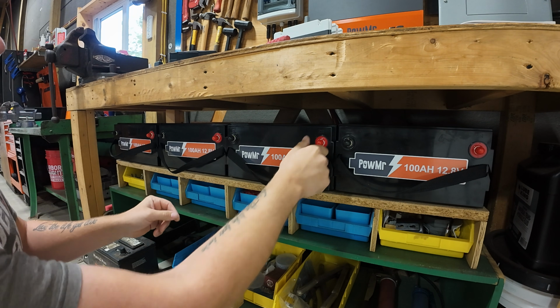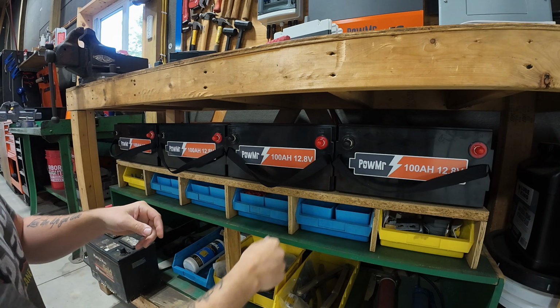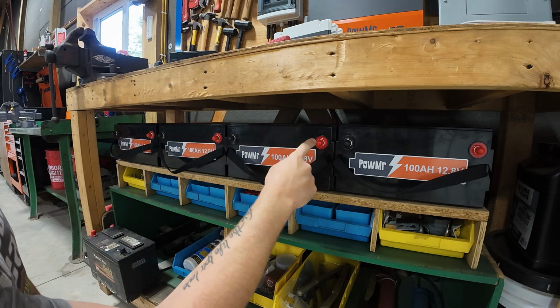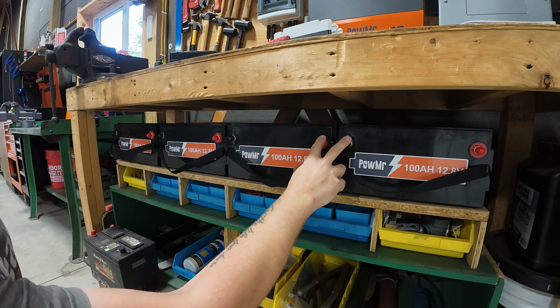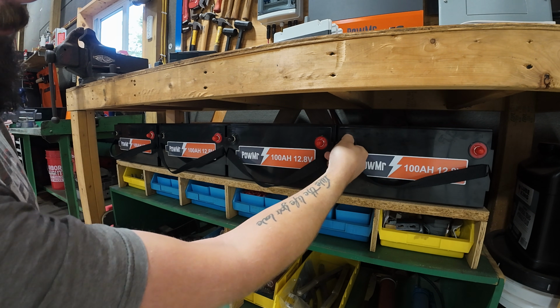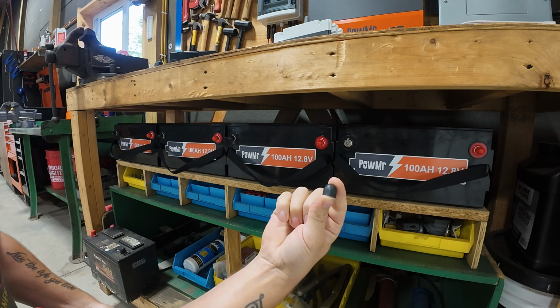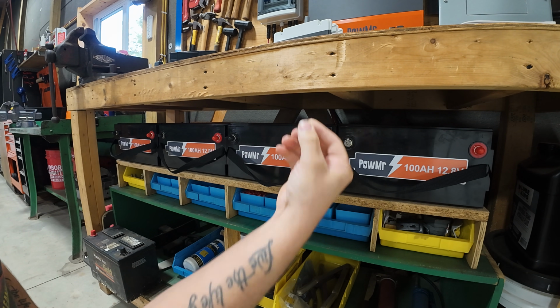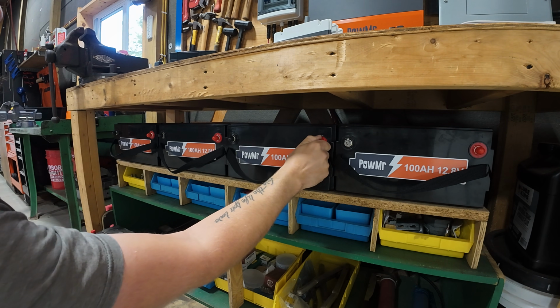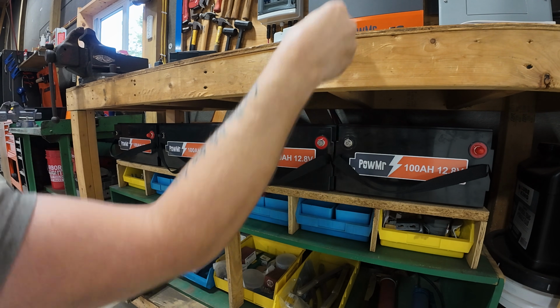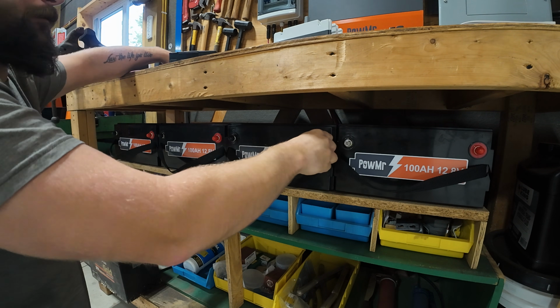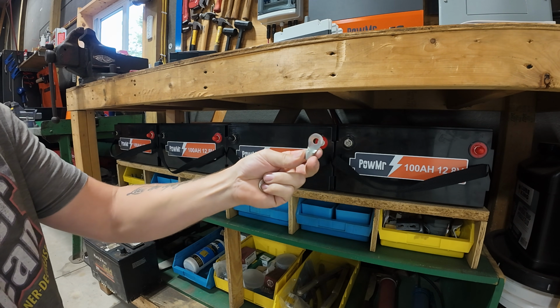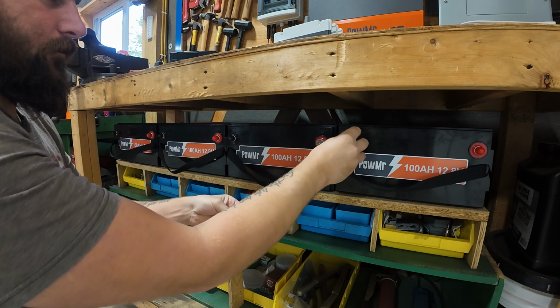So what I'm going to do now is remove 2 of these bolts, throw on a couple of eyelets, and measure to see how short of a wire I can get away with to link these 2 together. On these batteries there's just a little plastic cap you can take off, which protects the terminal from getting shorted out if anything gets dropped on the batteries. These pull right off, and we'll put them back on when we're done. Loosen these up, then we'll throw on one of our eyelets, same on this side.